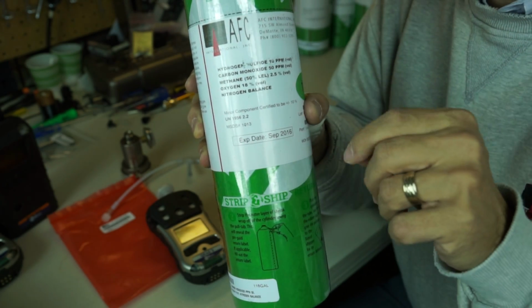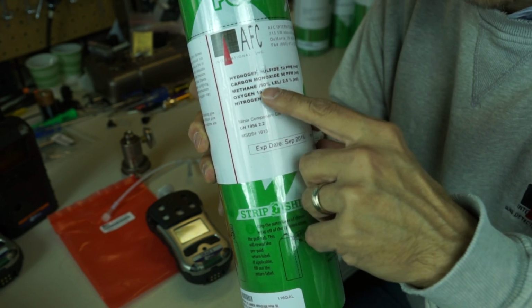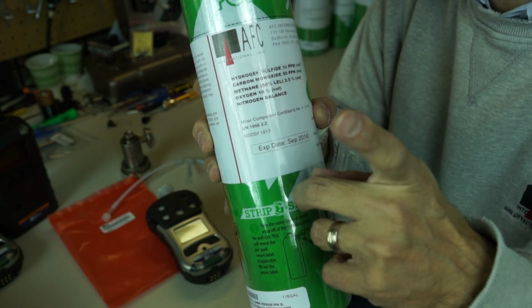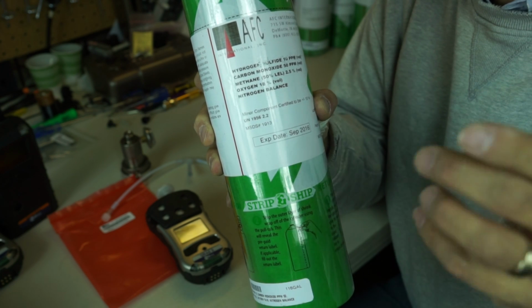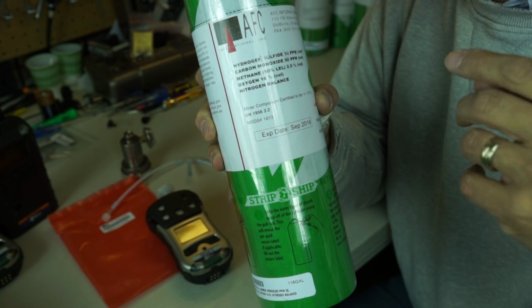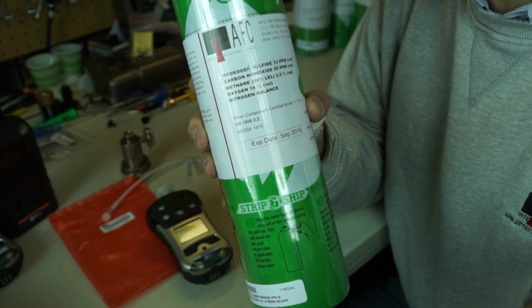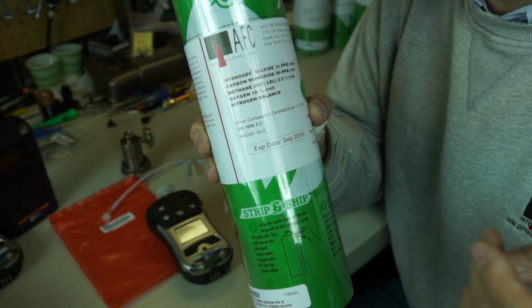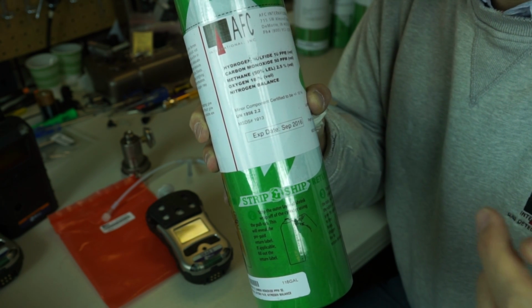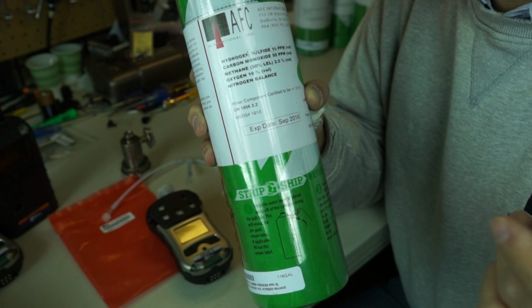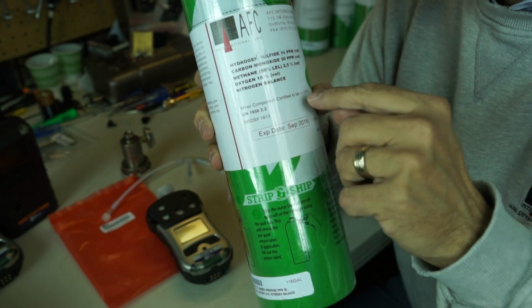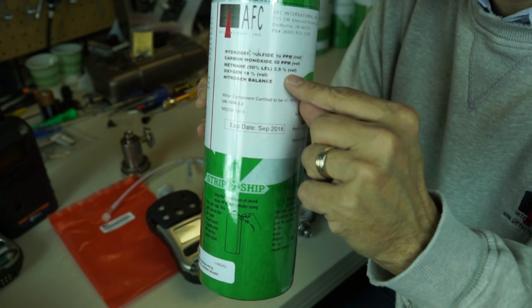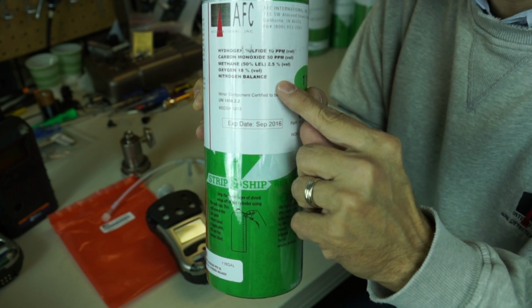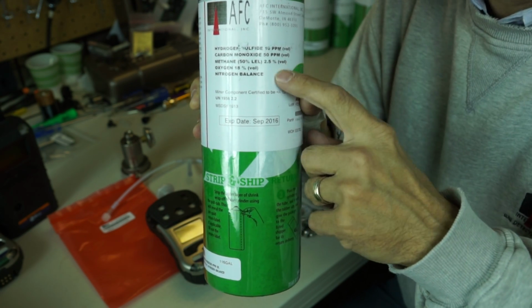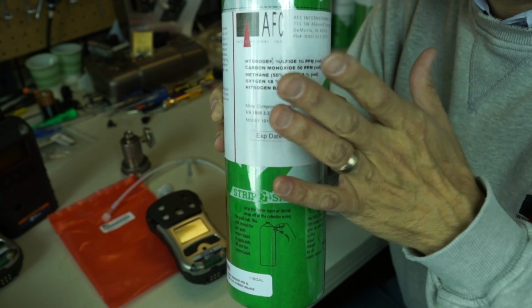But what's important here is we have to use the exact same concentrations the manufacturer asks for in their instrument. Now, the QRae 3 is asking for 50% LEL methane, 10 parts per million H2S, 50 parts per million carbon monoxide, and 18% oxygen. So all you have to do is basically match that up. And you can see here, my concentrations in this Portagas cylinder are exactly the same. All 4 in one cylinder, okay?